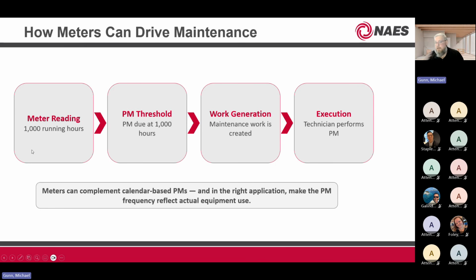So how meters can drive maintenance. Kind of repeating what I've talked about in the past, but the prime example is run hours, that's where I see it most. Meter readings are captured, you hit your 1,000 run hours on your turbine. You have a PM threshold, which I'll show you later in Maximo, where a PM is due at 1,000 hours. Maximo will automatically generate that work order, and from there your business practices for how you assign and complete it take over. But in the end, a technician performs that PM that was due at 1,000 hours.